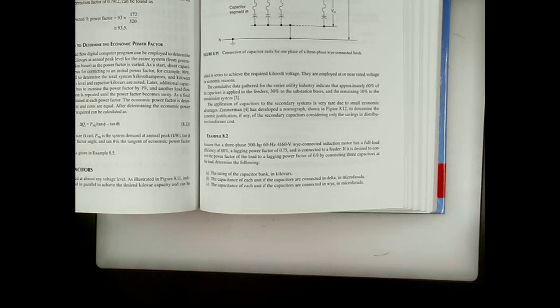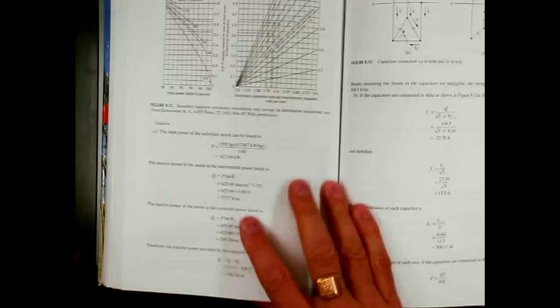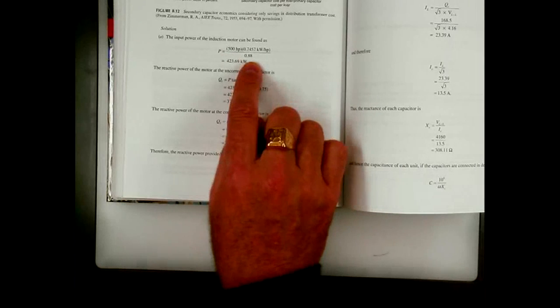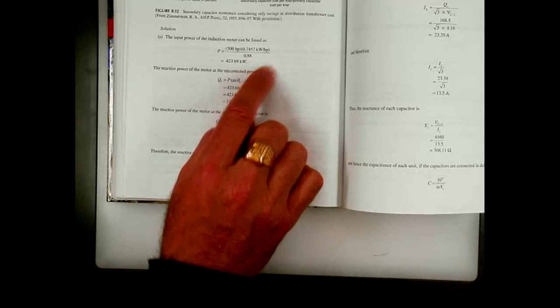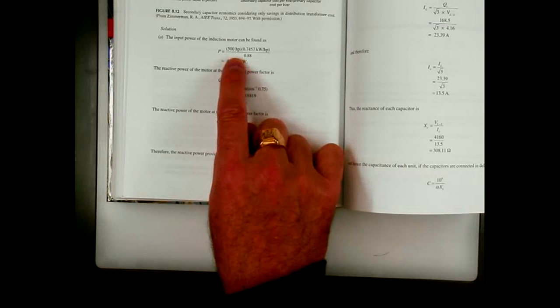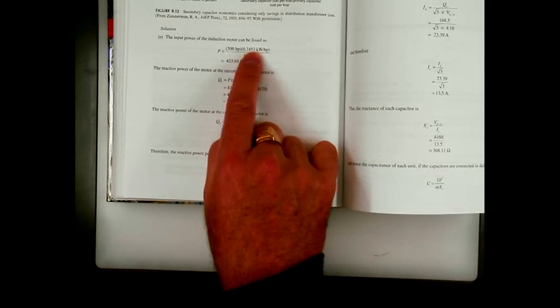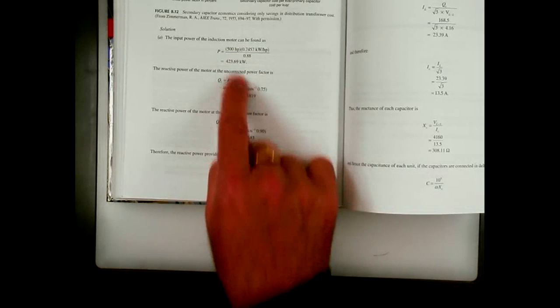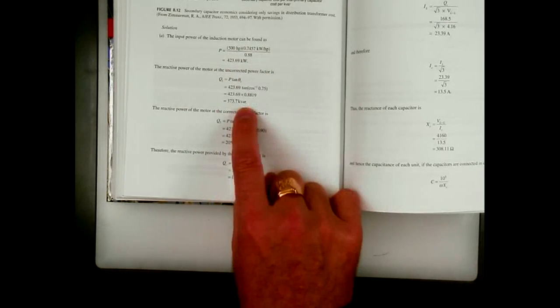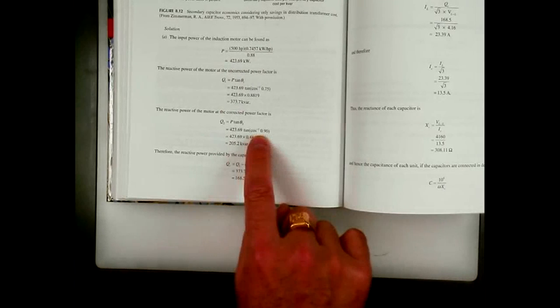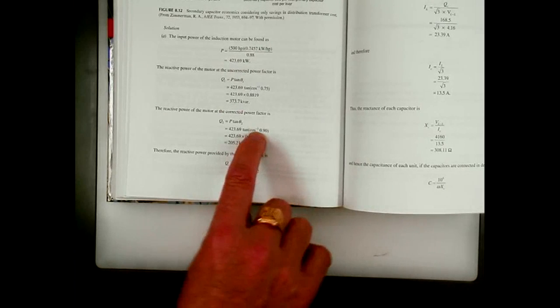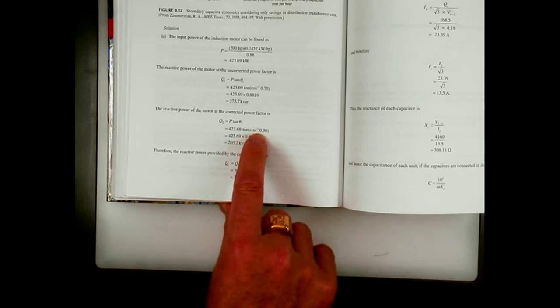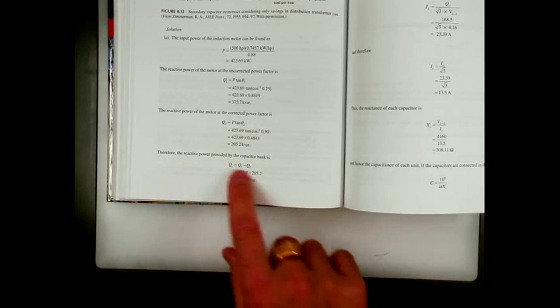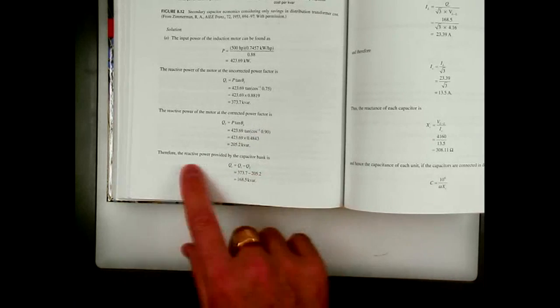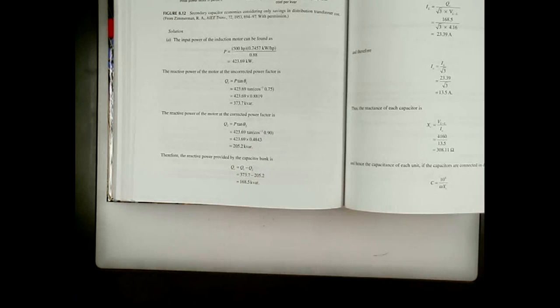So you have that wiggle room, and you don't go into compensation. That's basically P, right? This is what we did. The equation, when we convert from horsepower to kilowatt and divide by the efficiency, we calculate the reactive power, and then we calculate the desired power. Here we have that the reactive power provided by the capacitor bank is the difference.